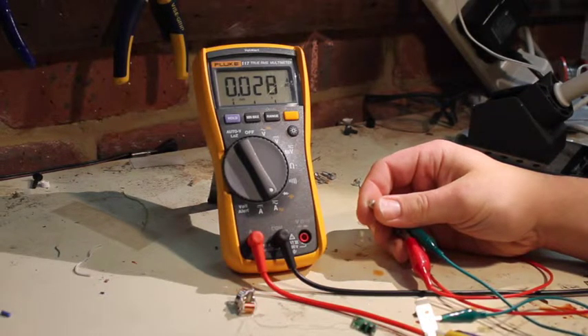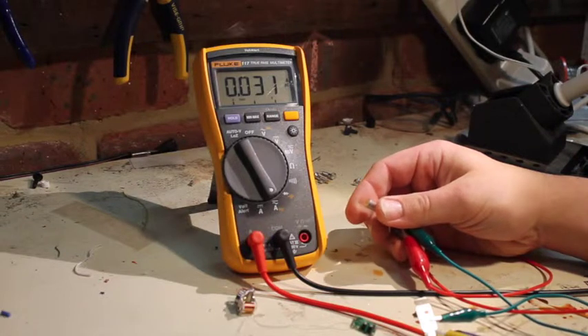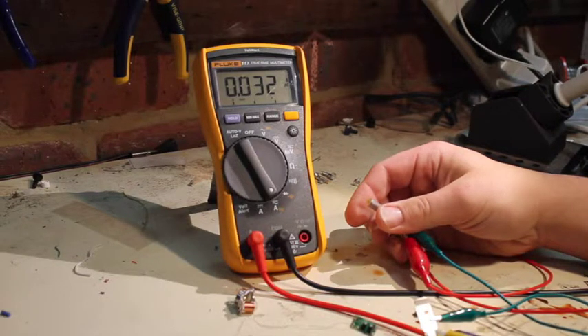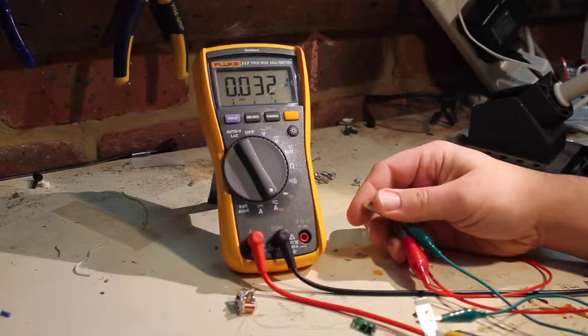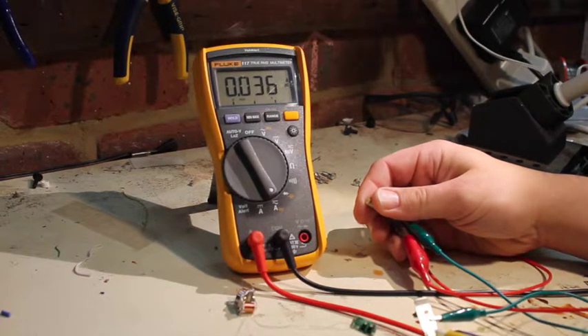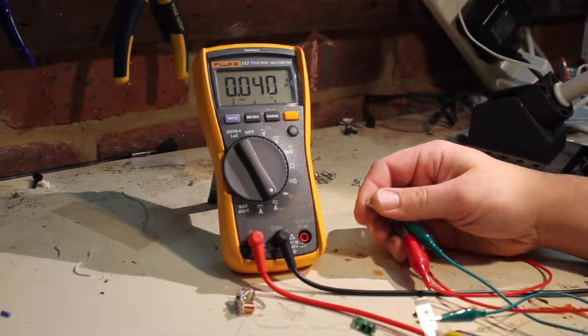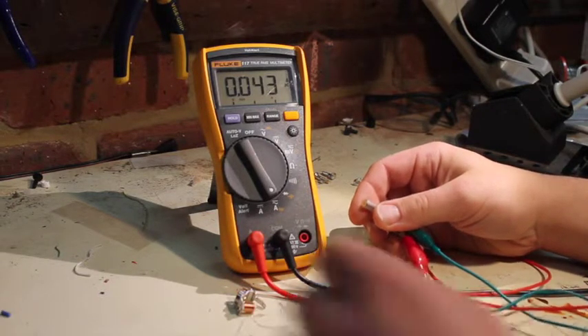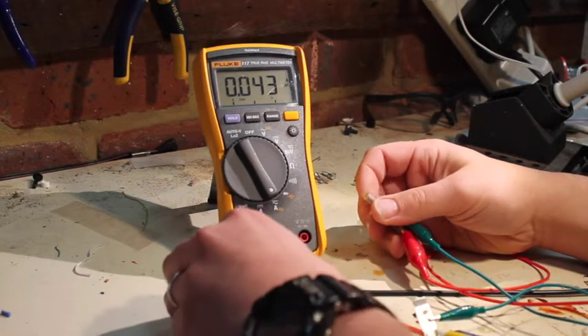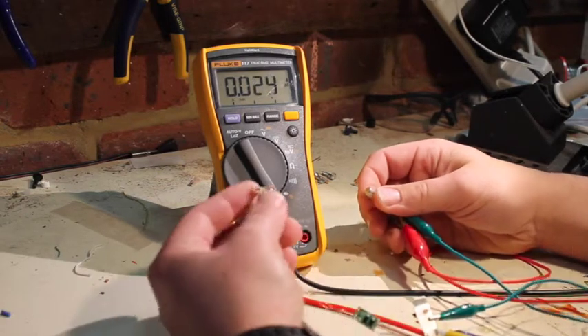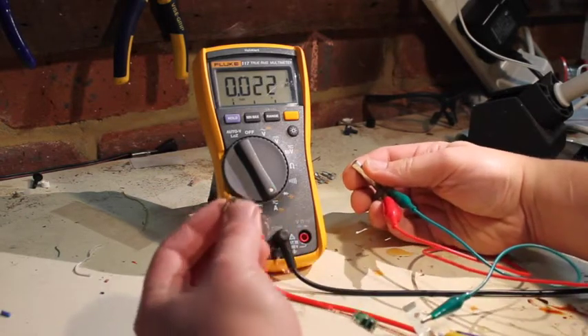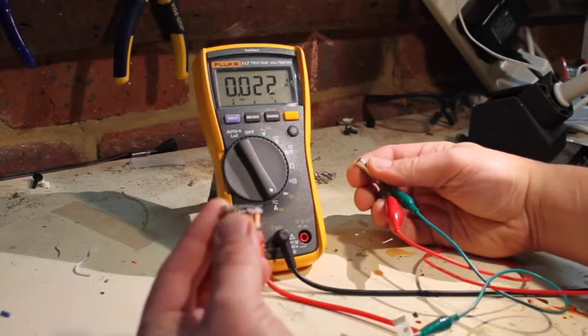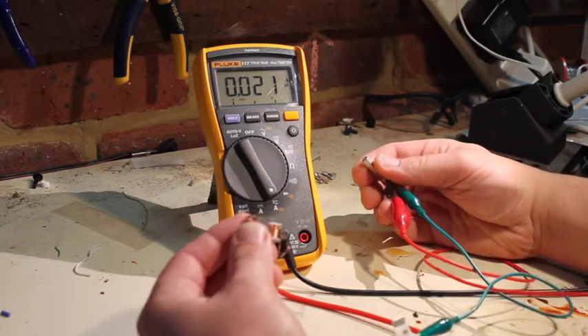28, 29, 30... so right now we've got an overcurrent situation and the RCD hasn't tripped. So 40 milliamps and what happened is the solenoid just released.